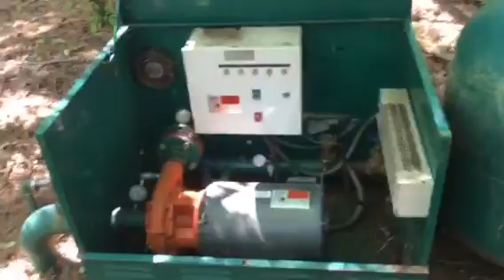Here's a brief overview of a very old Watertronic system that we've updated to allow us to communicate with it online. This was a contactor start with a simple pressure switch back in 2006. When I came here in 2009, it was working just fine. The unit got hit by lightning in 2010, and we have since eliminated everything inside that box.